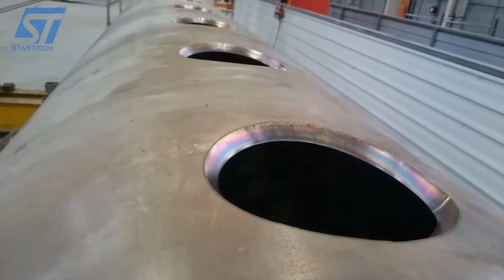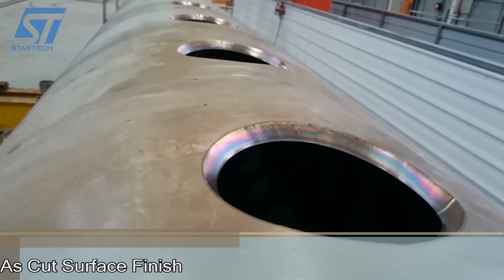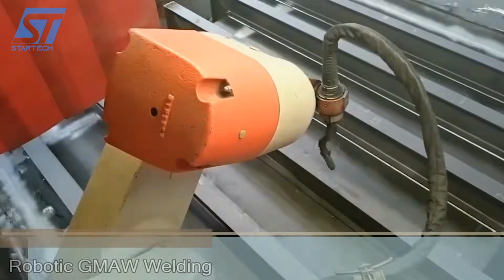This means every weld procedure is qualified, every welder is certified, and the finished vessel undergoes a hydrostatic pressure test, filled with water and pressurized to 1.3 times its rated working pressure before it ever leaves the shop.